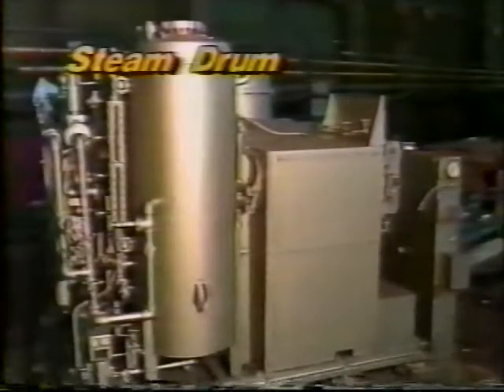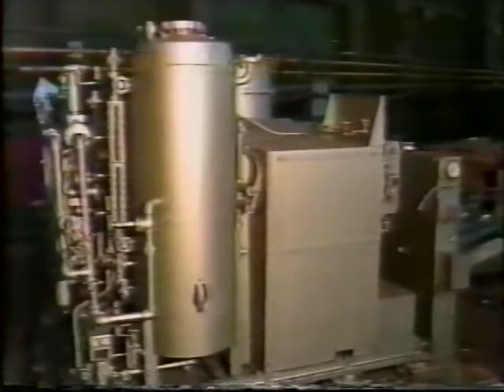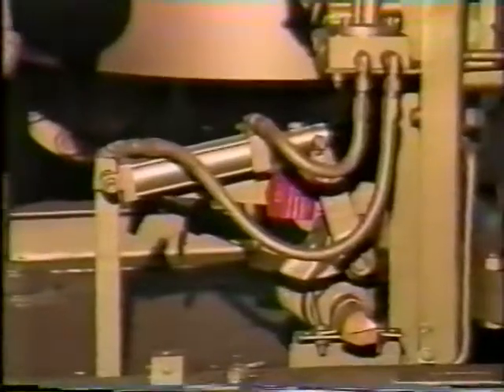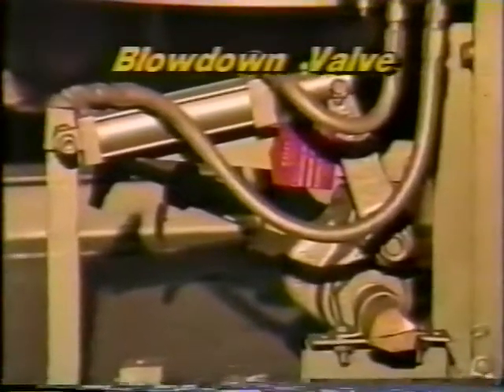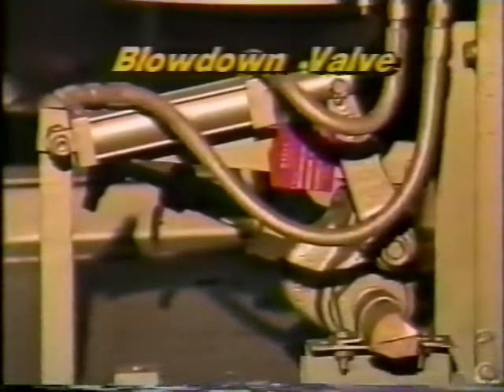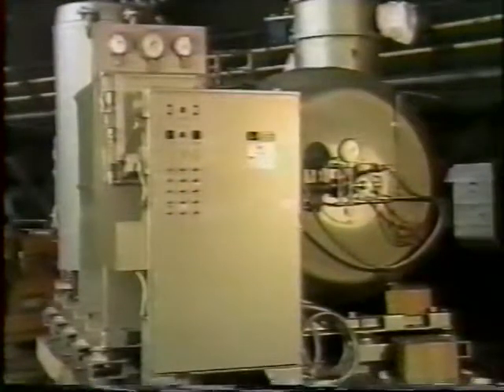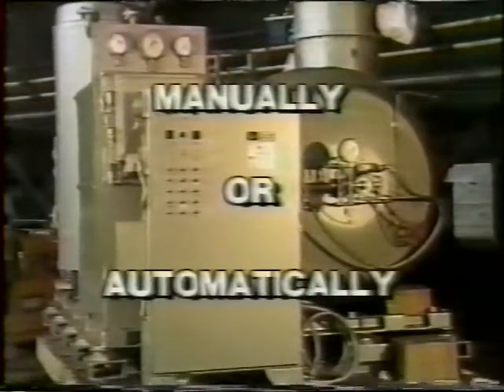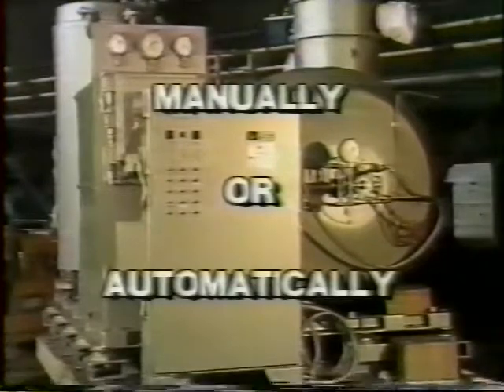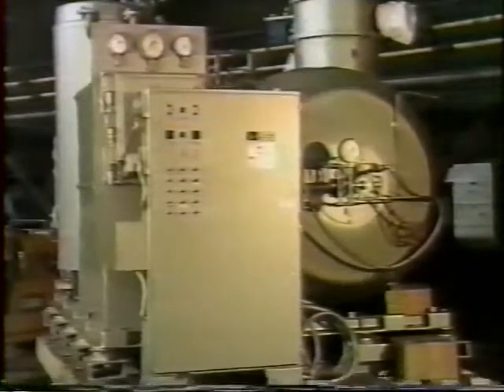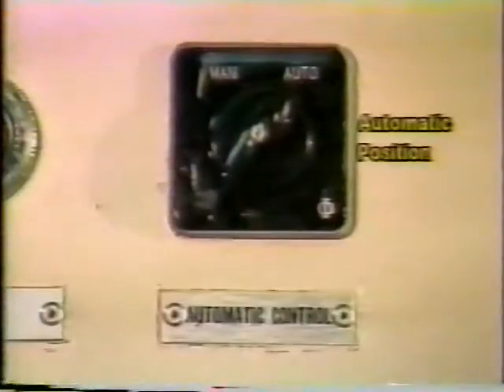Should the drum water level continue to rise, an upper level probe control activates the blowdown control to open its valve and prevent flooding the system. This boiler is equipped to operate manually or automatically for the initial filling of the drums and coils. In the automatic position, it is called on by a remote pressure switch mounted in the main steam header.